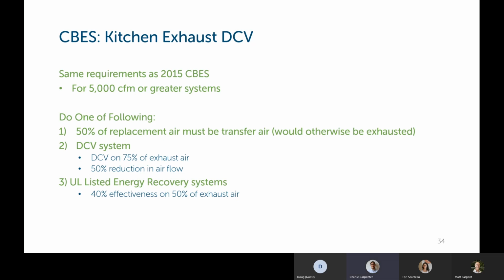Kitchen exhaust demand control ventilation are the same requirements as the 2015 Energy Code. For kitchen exhaust systems greater than 5,000 CFM, you would need to do one of these three types of ventilation strategies. The first is that 50% of the replacement air for the kitchen must be transfer air that would have been exhausted from the building otherwise.